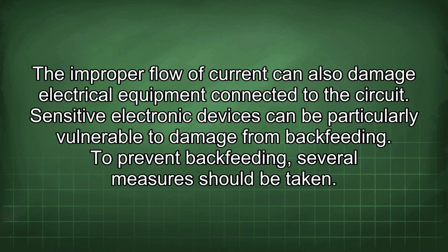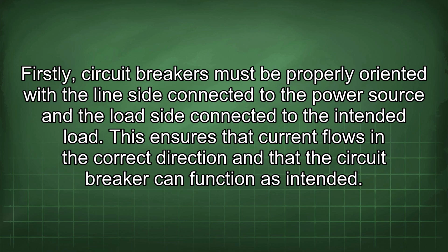The improper flow of current can also damage electrical equipment connected to the circuit. Sensitive electronic devices can be particularly vulnerable to damage from backfeeding. To prevent backfeeding, several measures should be taken. Firstly, circuit breakers must be properly oriented with the line side connected to the power source and the load side connected to the intended load. This ensures that current flows in the correct direction and that the circuit breaker can function as intended.